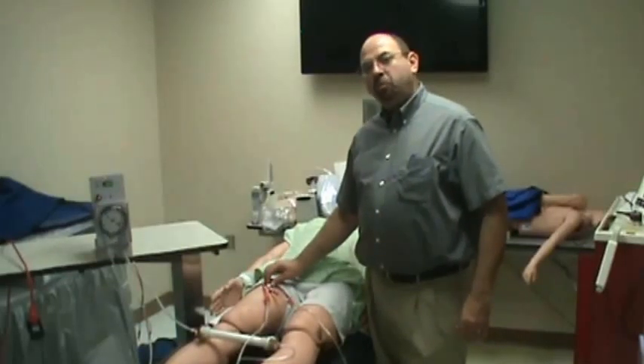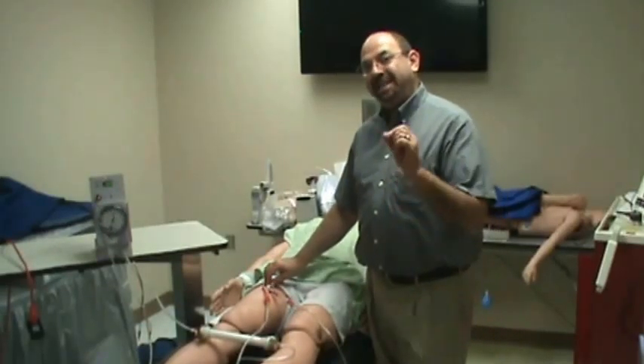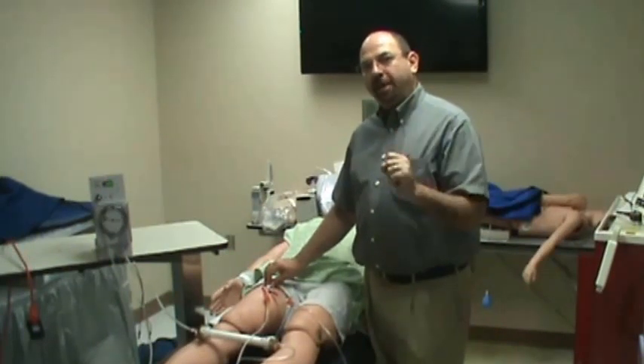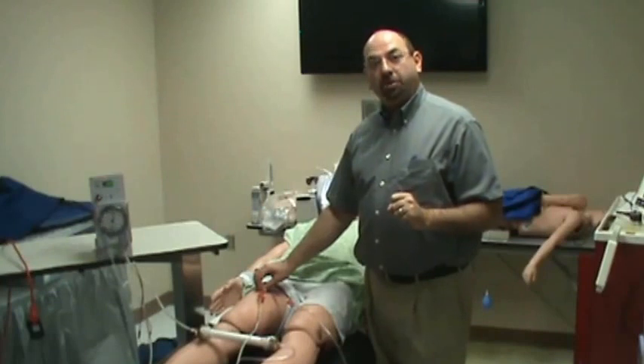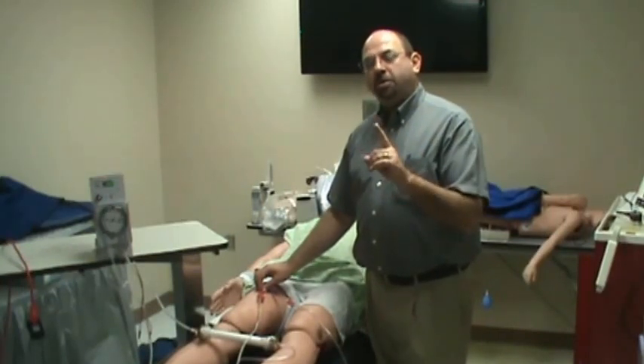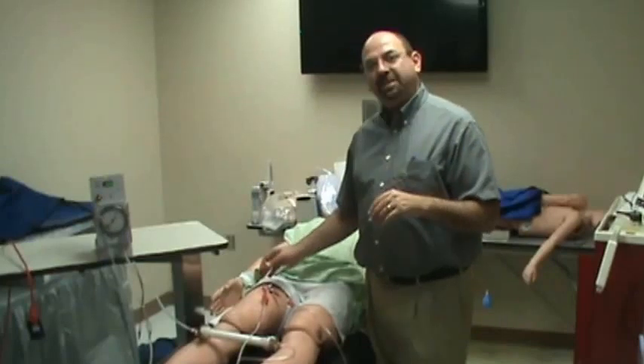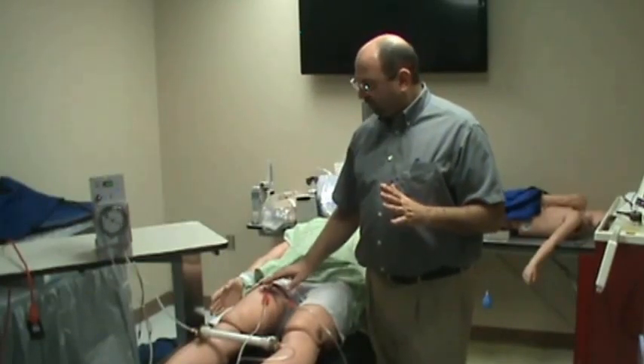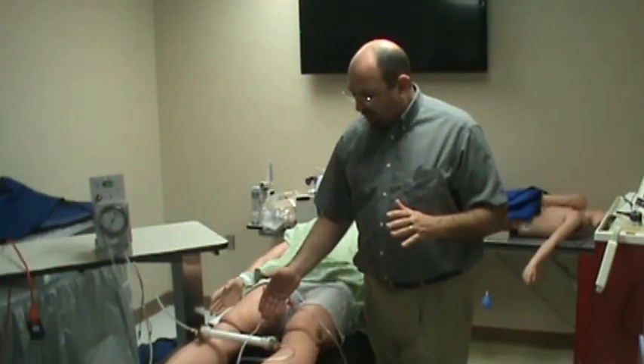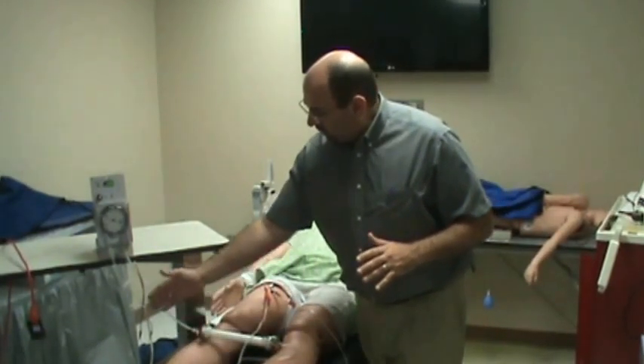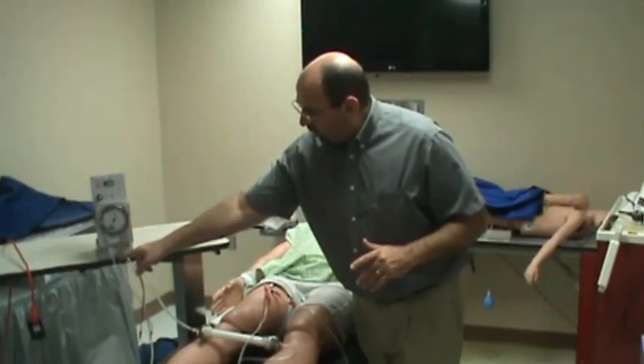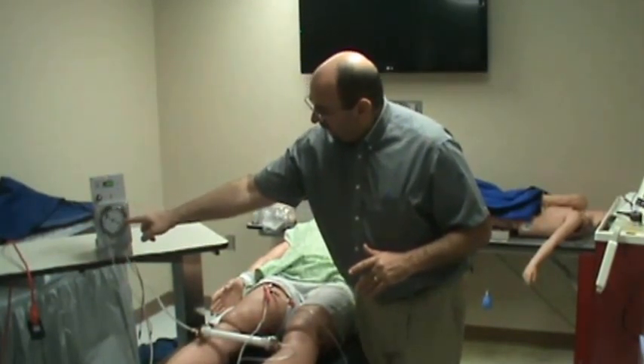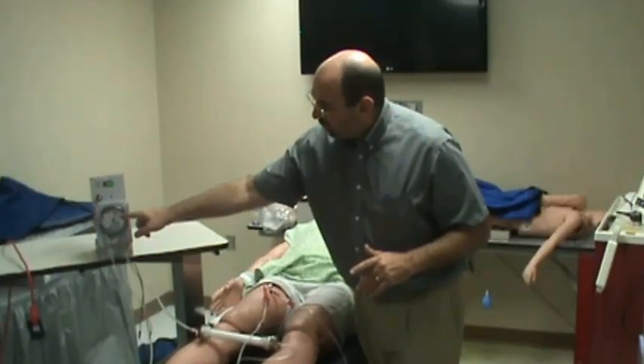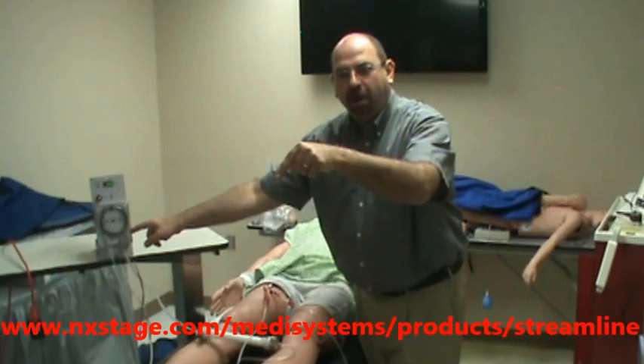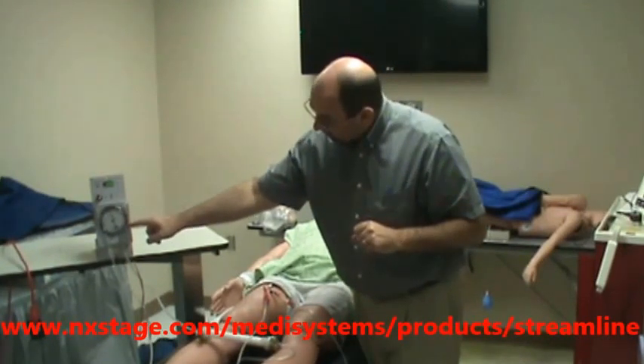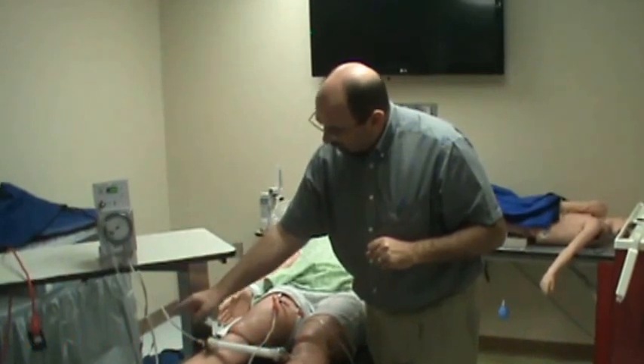This is a double lumen conventional dialysis catheter that is an intravenous catheter. Both ports are intravenous. The red limb is called the arterial limb, and it's a metaphoric arterial limb, where you pull the blood off. Blood is pulled out into the blood pump, and if you notice, it comes out here, and this pump is specifically designed with a tubing, and the name of the tubing is right here in front of you on the screen. And then blood comes out to the filter.